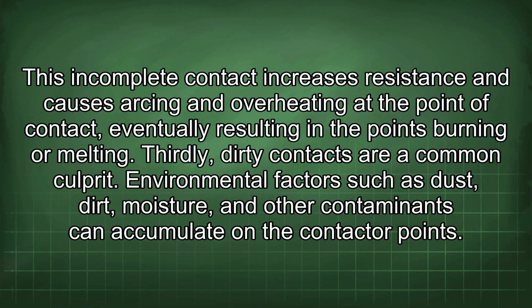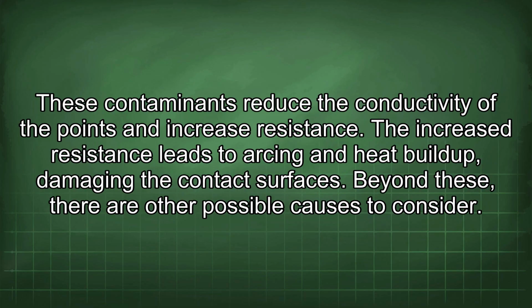Environmental factors such as dust, dirt, moisture, and other contaminants can accumulate on the contactor points. These contaminants reduce the conductivity of the points and increase resistance. The increased resistance leads to arcing and heat buildup, damaging the contact surfaces. Beyond these, there are other possible causes to consider.